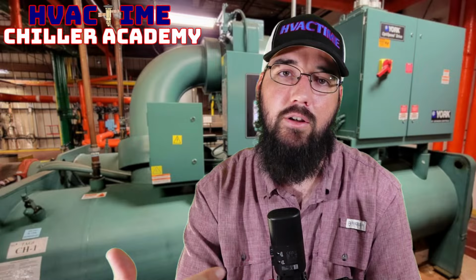Open loops get cleaned annually at a minimum. Some sites need more than that. And then you will do an eddy current every 3 to 5 years, depending on the site. And then closed loops will be opened up every 3 to 5 years in conjunction with that eddy current testing. And on a closed loop system, the only time you truly need to open the other side is if there's a problem, you need to plug a tube, something to that effect, or you've got a significant amount of trash you need to clean out of there. That would be the standard that we will go by.